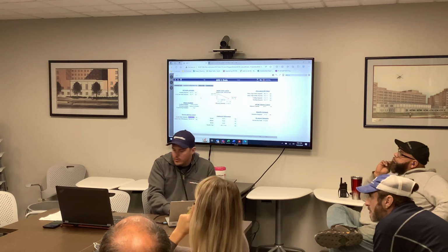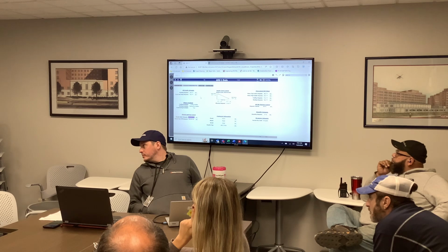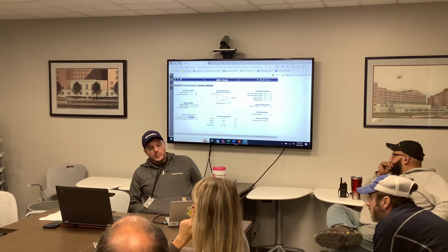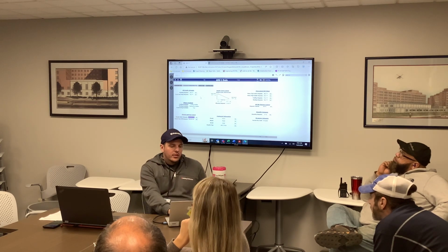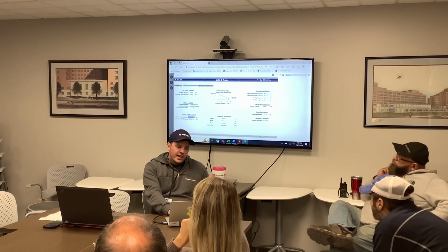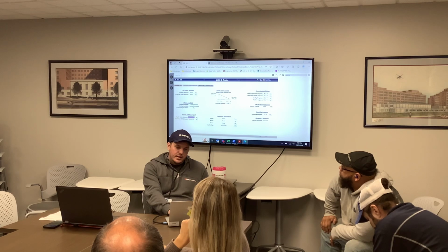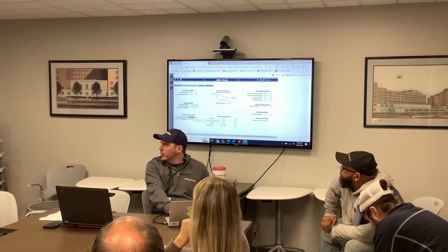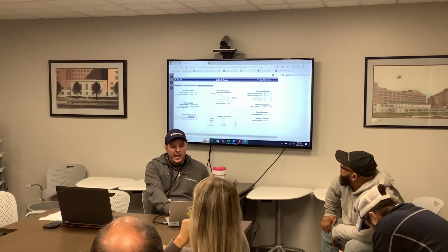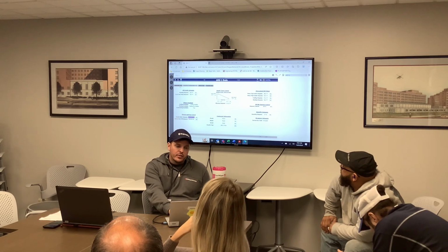I actually have a question for you. Sure. Is it set to give off a color if somebody overrides something? Yeah, it'll be purple. Cool. So this is an example. Right now, I have your supply fan static overridden. And we have some RFIs going out as to why that's overridden. For now, you can just leave it at 1.2. That's what the balancer left it at.